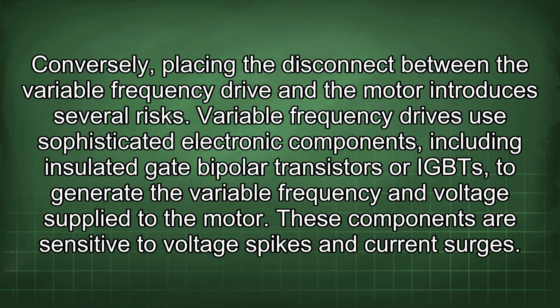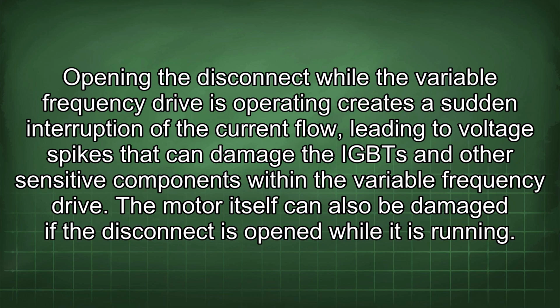Variable frequency drives use sophisticated electronic components, including insulated gate bipolar transistors or IGBTs, to generate the variable frequency and voltage supplied to the motor. These components are sensitive to voltage spikes and current surges. Opening the disconnect while the variable frequency drive is operating creates a sudden interruption of the current flow, leading to voltage spikes that can damage the IGBTs and other sensitive components within the variable frequency drive.